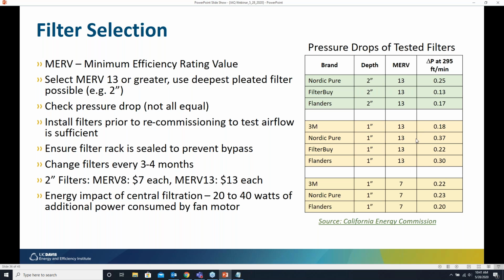So here's some data from the California Energy Commission. Highlighted in yellow are 1-inch deep filters that were tested. You can see they tested 3 MERV 7 filters and they show the pressure drop results. And then they tested 4 MERV 13 filters and they show the pressure drop results. And you can see that there are MERV 13 filters that have lower pressure drops than MERV 7 filters.